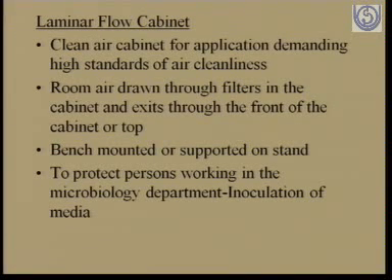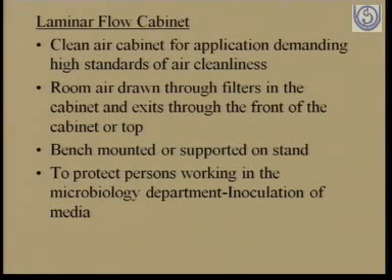Another important requirement from microbiology point of view is the laminar flow cabinet. Also from molecular biology side, this is a requirement, especially when you are inoculating the culture. If it is a tuberculosis culture, then again there is a requirement of having a laminar flow cabinet which draws air and extracts the air outside, and there are HEPA filters fitted in this laminar flow cabinet, which actually decontaminates the entire environment.